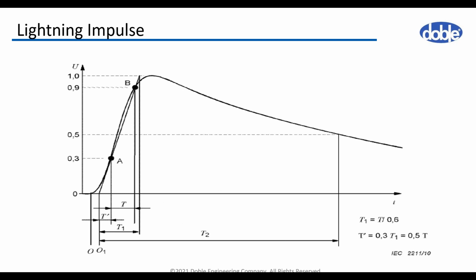This is how an ideal lightning impulse looks. The standard specifies a virtual front time of 1.2 microseconds with a tolerance of plus minus 30% and a time to half value of 50 microseconds plus minus 20%. When the neutral terminal is tested, the front time could be extended to 13 microseconds. Chopped wave lightning impulse should have a time to chopping between 3 and 6 microseconds, but in some cases a chopping time between 2 and 3 microseconds may be accepted.